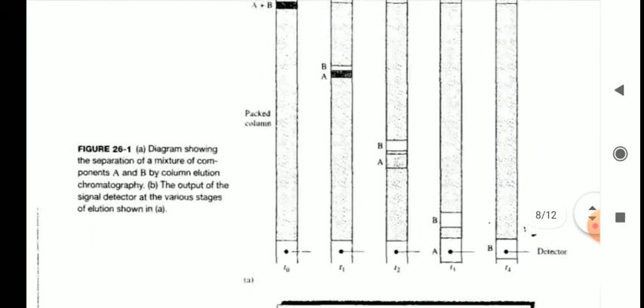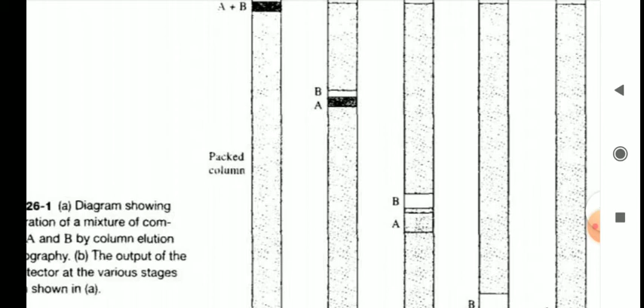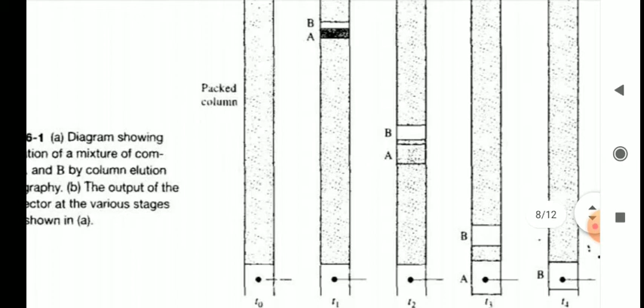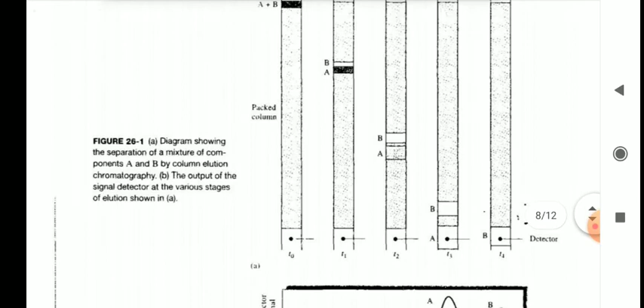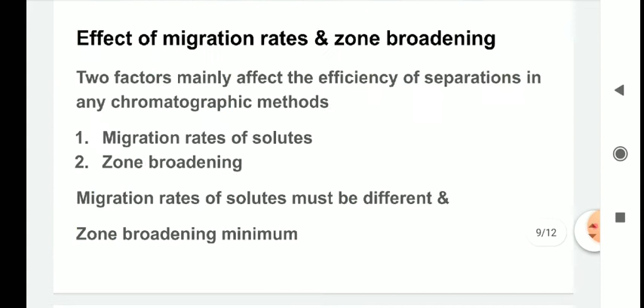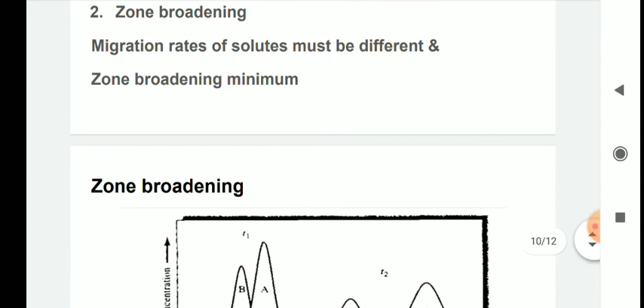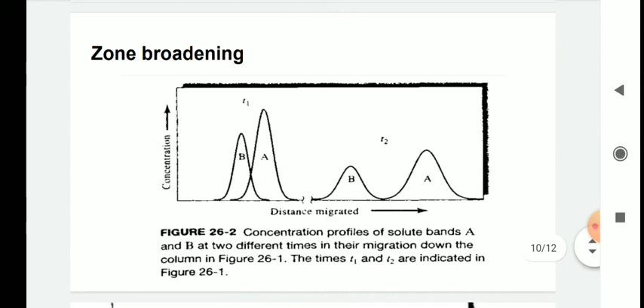Zone broadening, as we have seen, if you see in the second column shown, the zone broadening is less. In the third one, it is more, and in the fourth one the components are separated and the broadening is quite large. Now this zone broadening is not avoidable, but you have to try to reduce it. If you had placed the detector inside the column at time t1, you would not have got the separation, but the peaks would have been narrow, but overlap would have been there. Now, as you move down in time, the components have got separated, but the bands have become broad, and you are getting zone broadening.